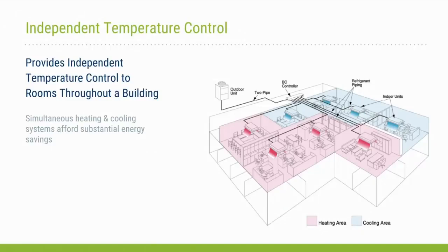VRF systems control with precision. The flow of the refrigerant is varied to each of the indoor units to match the space requirements. And the outdoor unit includes an inverter-driven compressor. This combination of control gives these systems the ability to have a broad capacity range from as low as 10% to 100%. Next slide, please.